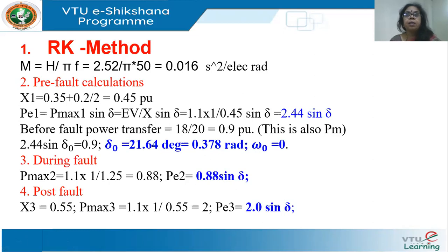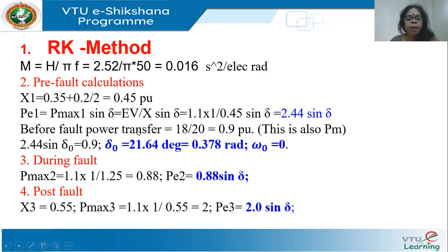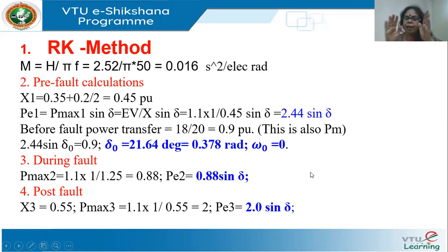ω₀ = 0 because omega here represents the change in angle, dδ/dt. Don't mistake ω₀ = 0 to mean the generator is stationary — it means the generator is running at constant speed, so delta is constant. Post-fault, one of the lines is cleared. The line reactance is 0.2 (one line removed), plus 0.35 gives 0.55. So P_max post-fault is 2, and P3 = 2 sin δ. These initial values will be used for both Runge-Kutta and Euler's method.